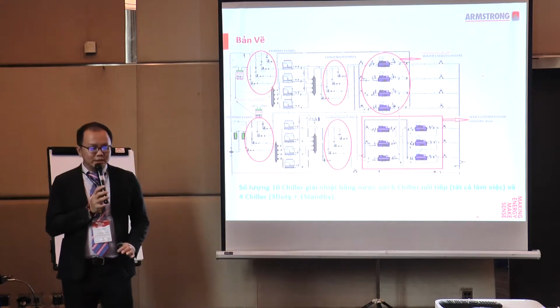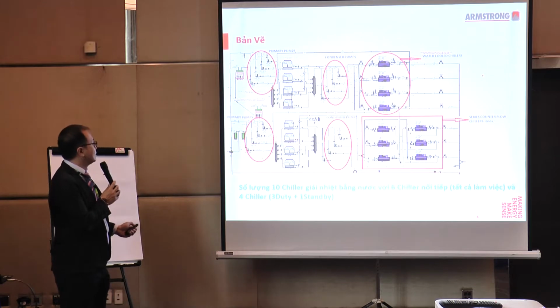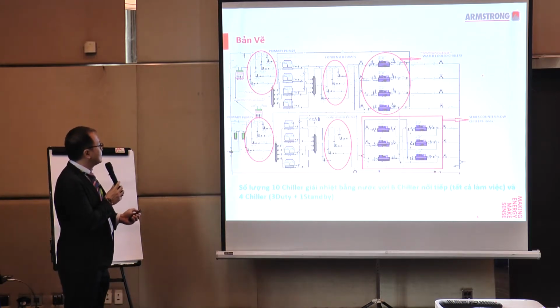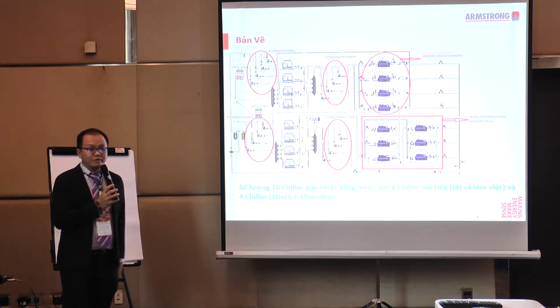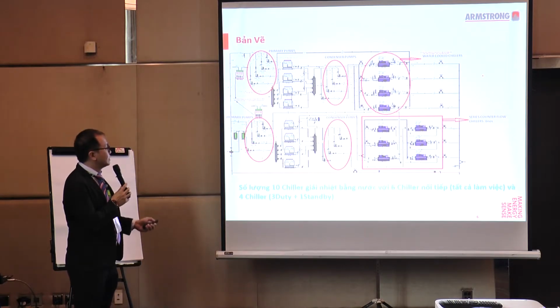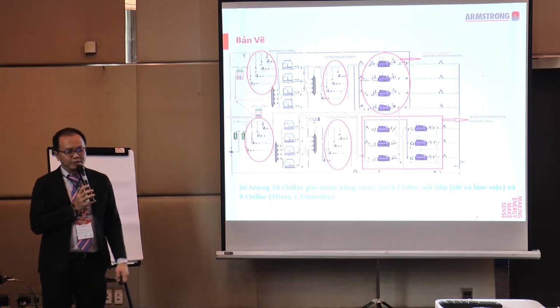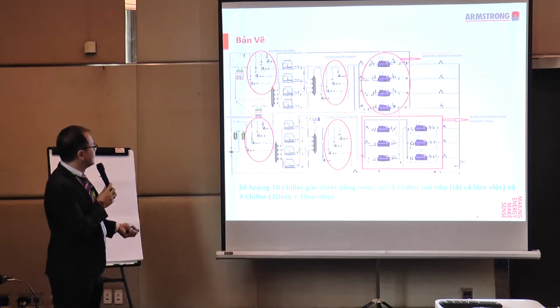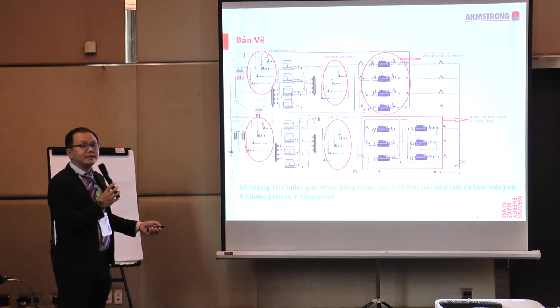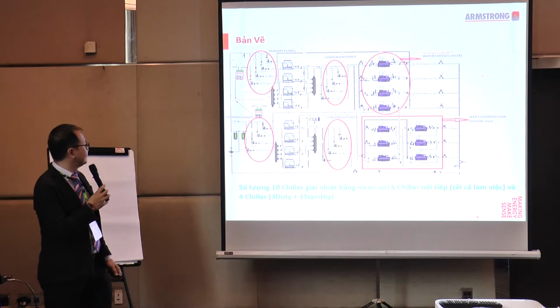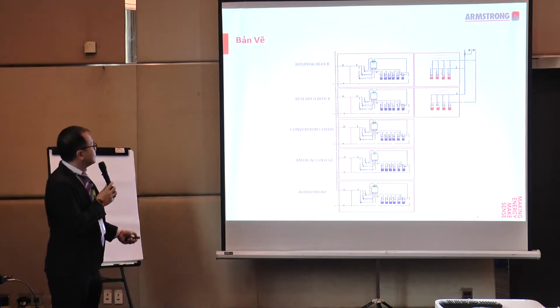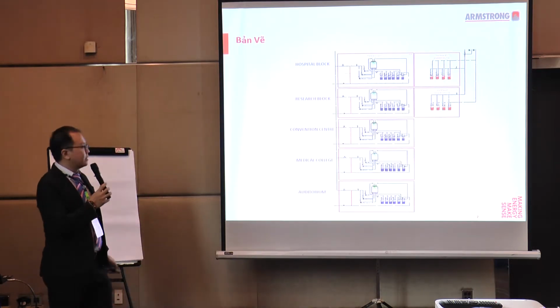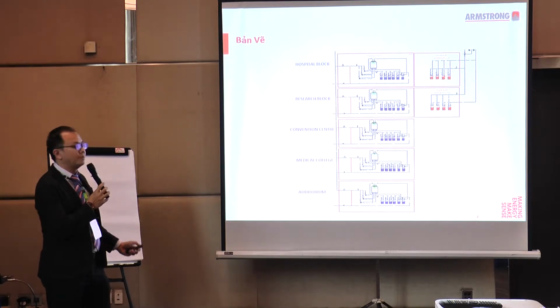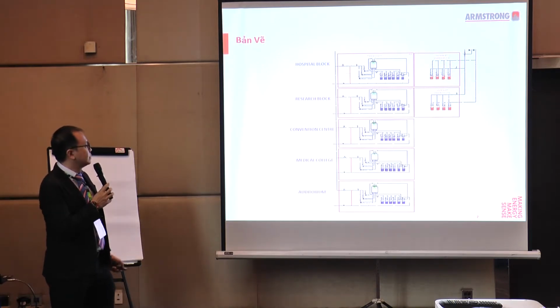So this is originally the design that the drawings encompassed. You can see here the primary pumps that support the water-cooled and the counterflow chillers, and then the condenser pump is attached to that. So in total, you have 10, 4 plus 6. And then this is the drawing of the secondary and tertiary, which are the 5 building blocks that are being supported.